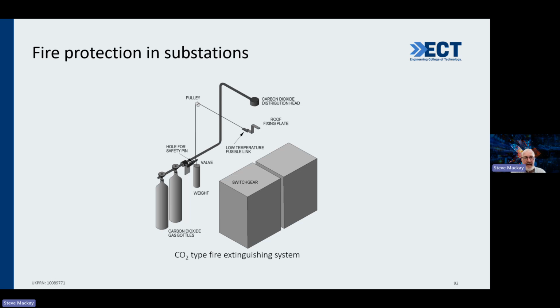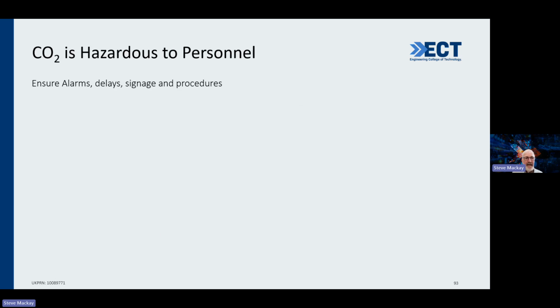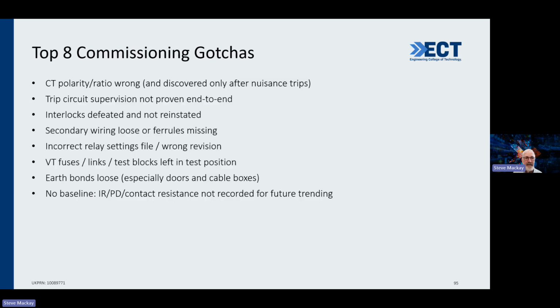Yeah, absolutely. Carbon dioxide is not just something that puts the fire out, it is actually hazardous to you as a human being. So watch out for that because it can be a problem. It's hazardous to personnel, and people often don't pick that up. They think carbon monoxide is hazardous, and that certainly is, but carbon dioxide is too. So ensure alarms, delay, signage and procedures are all put in place. That's really important.